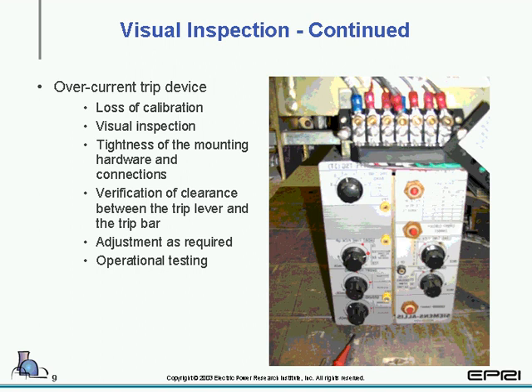We'll take a look at overcurrent trip devices. Again, as we spoke about in Section 1, we move from electromechanical to more modern types, and then finally on to programmable or logic-based. You cannot visually inspect them alone. You must actually test them to verify that they are operating and in good condition. And we have more about that when we take a look at Section 3 next week.